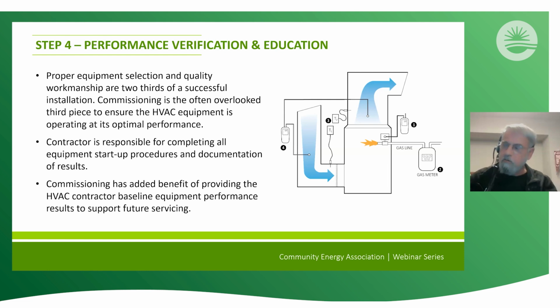It's also a requirement in a lot of cases to get your warranty. If you have a compressor failure or something like that, something major, you're going to the supplier or the manufacturer under warranty. They want to know, okay, let's see the commissioning report. Let's see your startup procedures. What was the compressor doing, for example, when you started it up? And that helps them determine whether this is a pilot error or it's a legitimate warranty issue.